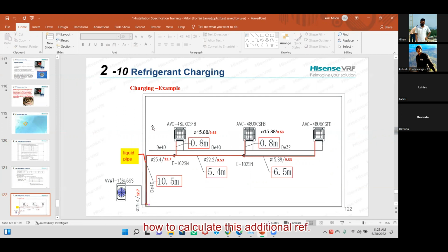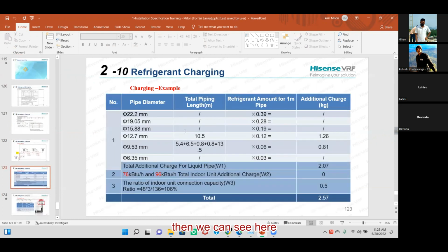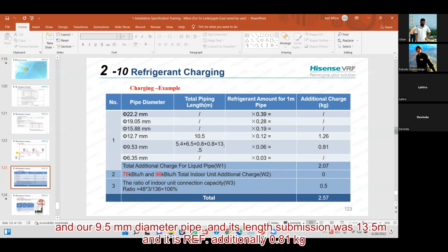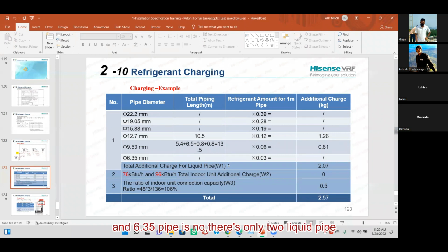How to calculate this additional refrigerant? Here we can see our 12.7 mm diameter pipe, and its length was 10.5 meters. Then the additional refrigerant required for this pipe is 1.26 kg, and for our 9.53 mm diameter pipe, the length summation was 13.5 meters, and the additional refrigerant required is 0.81 kg, and for 6.35, no, there are only two liquid pipe sizes.